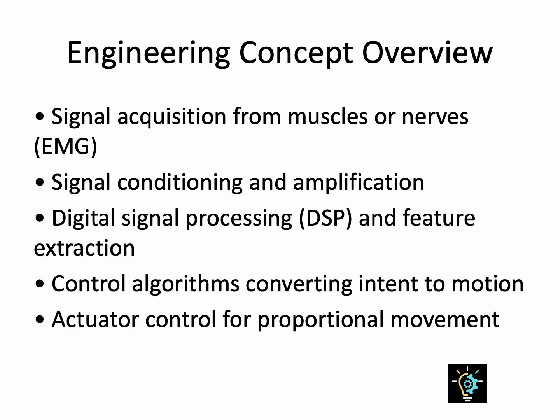Every prosthetic arm begins with signal acquisition, the process of capturing bioelectric data from the user. These signals, often in microvolts, are then amplified and cleaned up using analog filters before being processed digitally. Engineers use DSP, digital signal processing, to extract patterns that correspond to specific muscle actions. From there, control algorithms translate those patterns into smooth, proportional movement of motors and actuators. Think of it as designing a feedback system that interprets intent in milliseconds. Each subsystem must minimize latency, avoid noise, and ensure stability under varying loads.